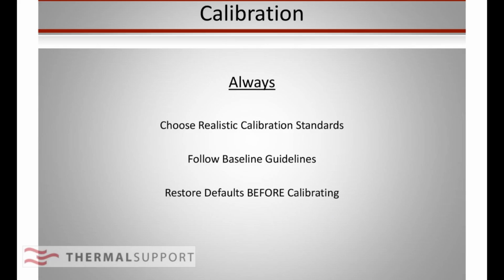But again, always use realistic calibration standards, follow baseline guidelines, and then when you're ready to go, restore your defaults before you start calibrating. In your calibration screen, you'll see restore up on the top file menu bar. You tell it to restore all. You save and apply that as whatever you want to call it. Don't call it default. I like to use the date. It just shows us when it is. You don't have to say DSC unless you want to see it under the Explorer, but it'll come up as the only calibration with the DSCs. But at any rate, name it something besides your default calibration files.